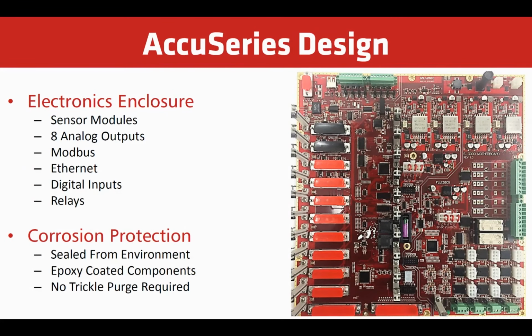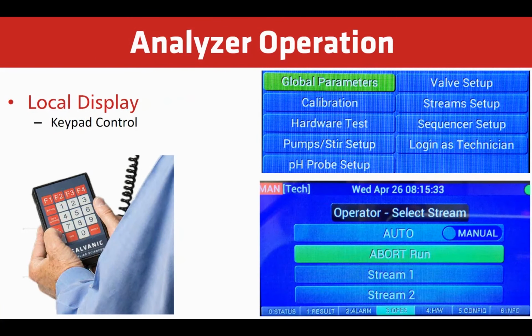This shows the motherboard or backplane board that all of the sensor modules plug into. It allows for 8 analog outputs, has Modbus and Ethernet capabilities. It has various digital inputs and programmable relays. Again, the boards are sealed with an epoxy coated sealant to avoid any humidity or condensation forming that will create corrosion, or if it's in an environment where corrosive vapors are present, they will not attack the boards. So, analyzer operation, it's all controlled from a local keypad control that's on the analyzer.